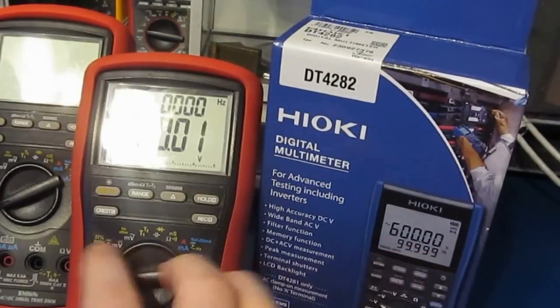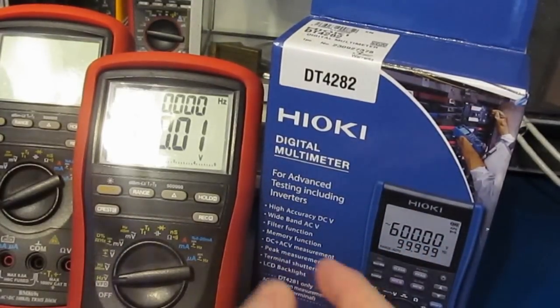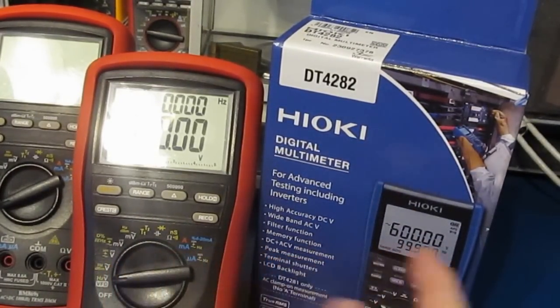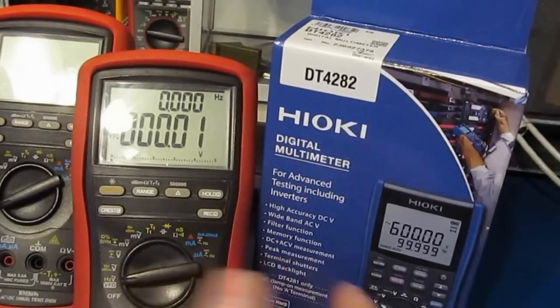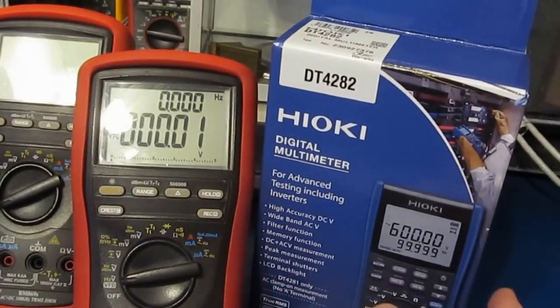Again, I had mentioned that both meters measure conductance. If we look at the normal resistance mode, this meter can only read up to 50 meg, where this Hioki can read up to 600 meg.